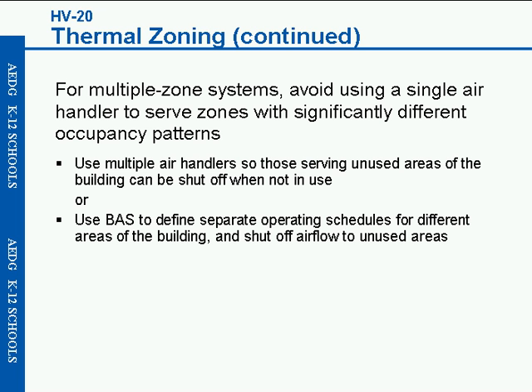For the multiple zone systems, there are recommendations for avoiding using a single air handler that serves zones with significantly different occupancy patterns. You'll want to provide a separate air system for the gym and a classroom, mostly because those occupancy patterns are usually significantly different, and there's savings to be had for systems that can provide heating, cooling, and ventilation to each one of those zones as needed.